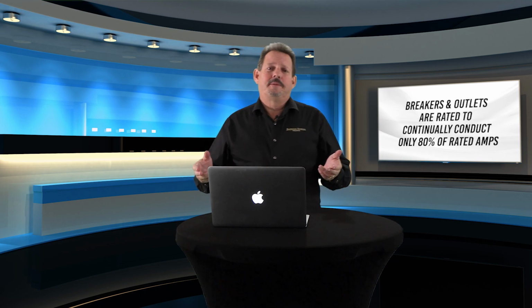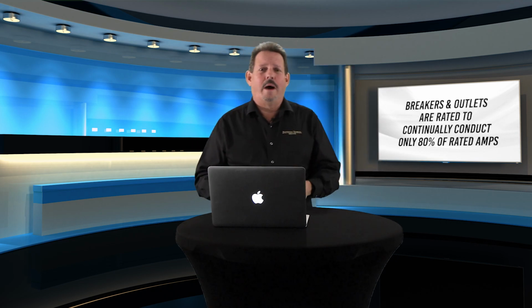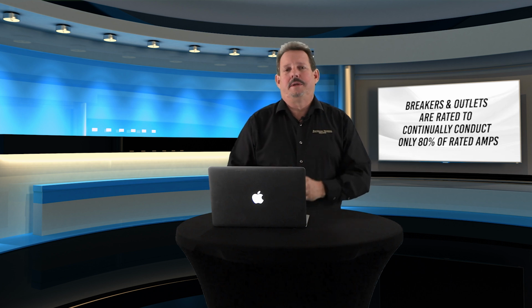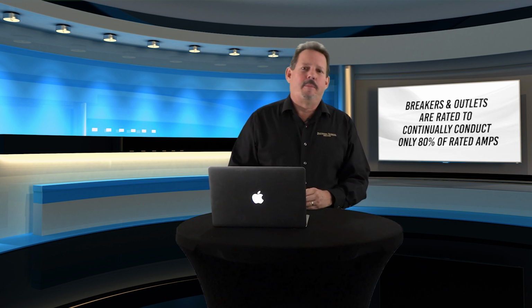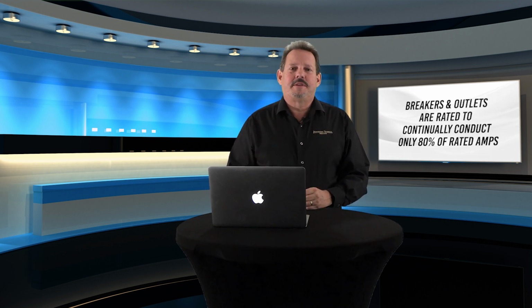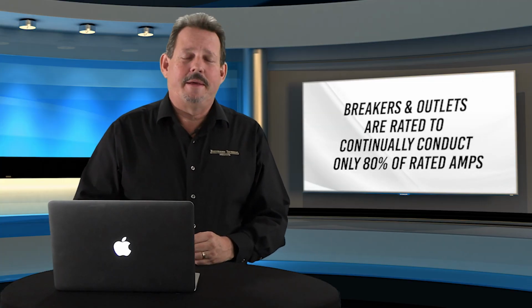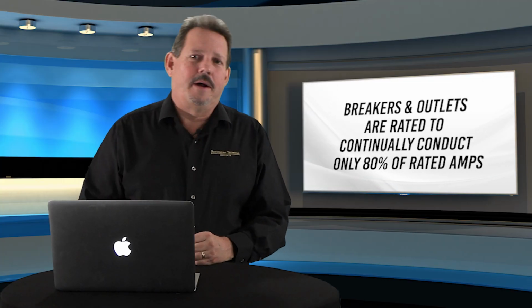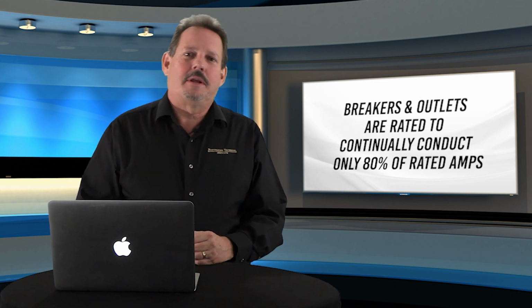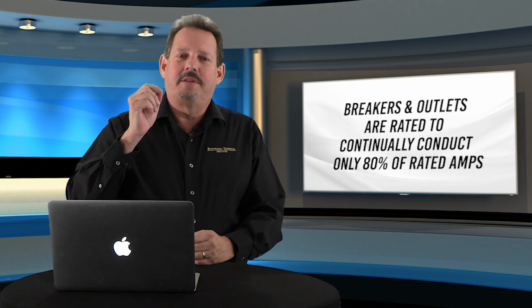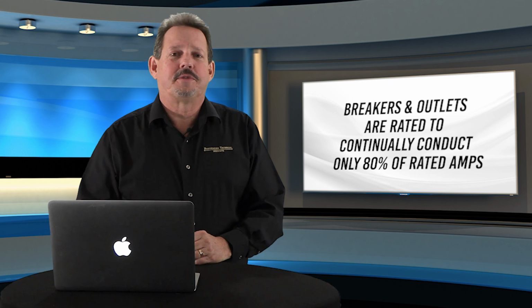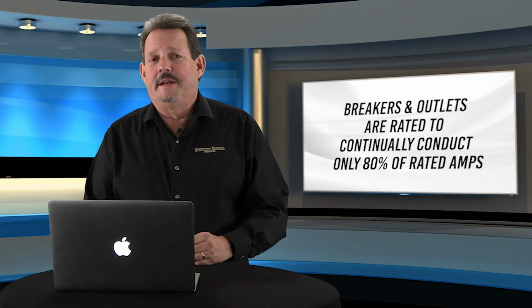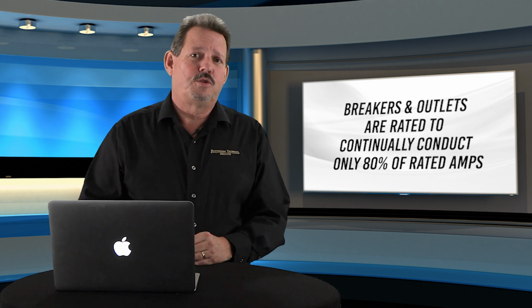Breakers and outlets are only required to continually support the rated amperage at 80%. So if you have a 20 amp circuit breaker or a 20 amp outlet, that means only 80% of that 20 amps is designed for continuous use, which of course is what we're going to do. So literally you only have 16 amps on a 20 amp circuit breaker or outlet, and on a 15 amp circuit breaker or outlet you're looking at only 12 amps.